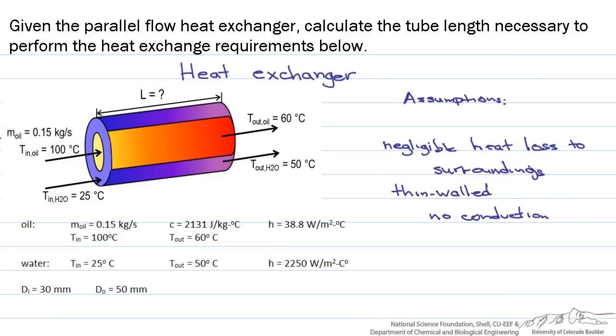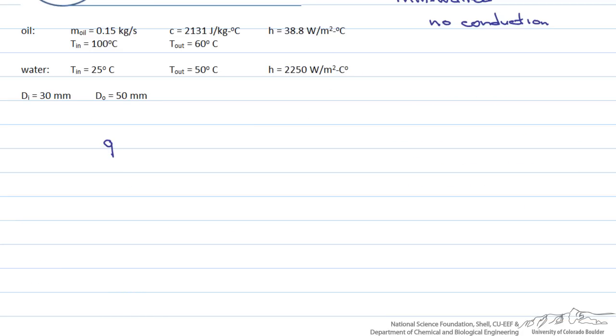Let's start with our governing equation. The heat transfer rate is equal to the overall heat transfer coefficient times the wetted surface area times our delta T log mean. We use a delta T log mean because delta T — the difference between the hot and cold temperatures — varies along the length of the heat exchanger, so we use a log mean temperature.